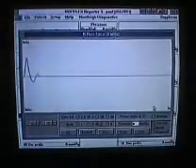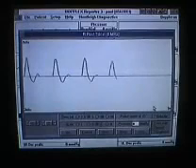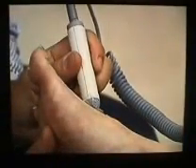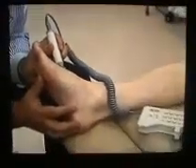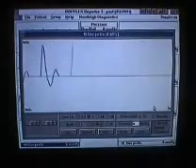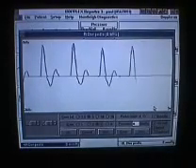It's important to understand how arterial waveforms are produced from the Doppler. The probe detects the Doppler-shifted frequencies reflected back from the moving blood cells and converts this into a sound produced by the loudspeaker. Higher blood velocities are heard as higher-pitched sounds. The angle of the probe will also influence the Doppler shift frequencies detected, so it's important to hold it at approximately 45 degrees. This is a characteristic normal arterial waveform in the lower limb.